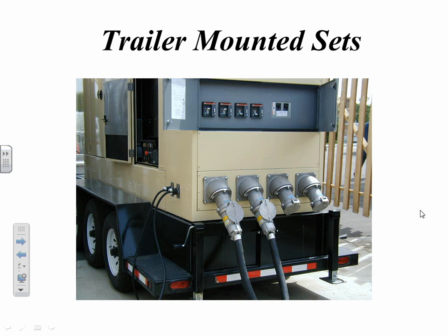And actually, this is what they call a high Y. You actually have these coils parallel to the low Y. So I do that a little wrong. So right now, between line 1 and neutral, you'll have 277. And between line and line, you'll have 480. For what I've drawn. 277 is a very common industrial lighting voltage used in warehouses and stuff.